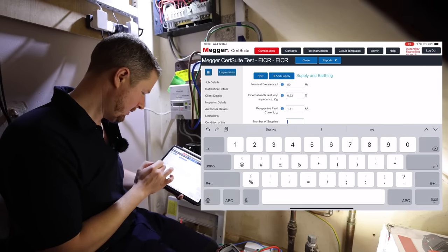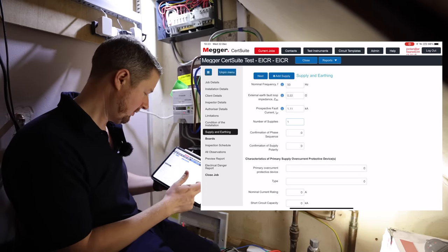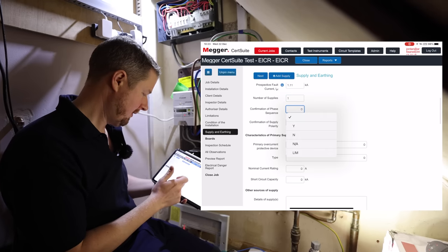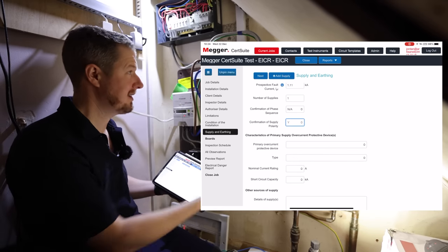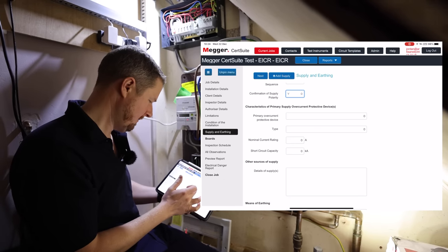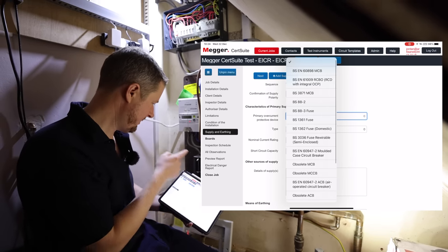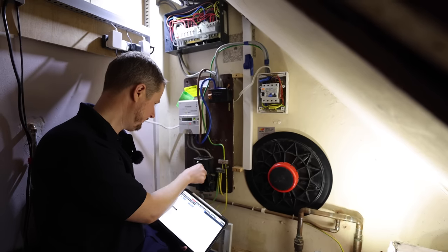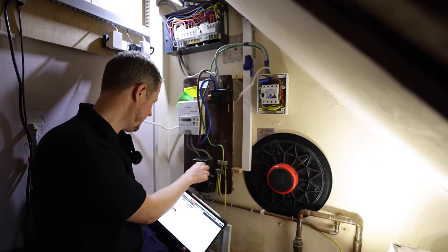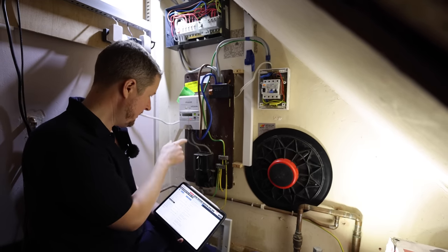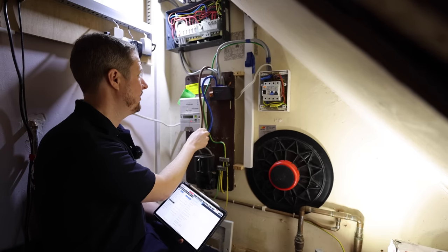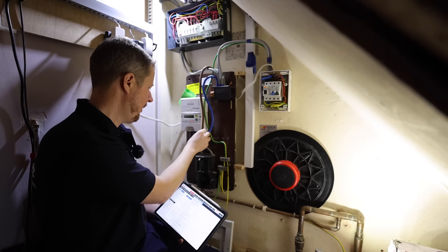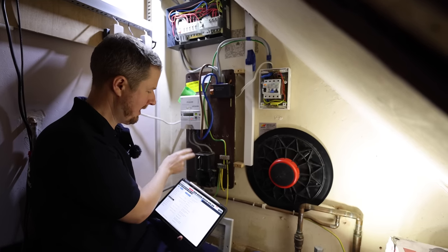What we'll do as well is we'll do the same but we'll do it live to neutral. So the highest reading is the first one that we did, the prospective earth fault current, which is 1.11. So put that in. Number of supplies is one, it would be more if you had like a generator or some other alternative source of supply. The phase sequence is N/A, supply polarity is correct, we verified that when we did our Ze test.